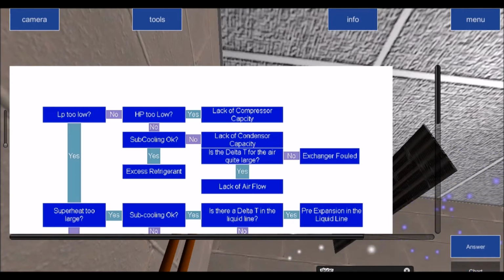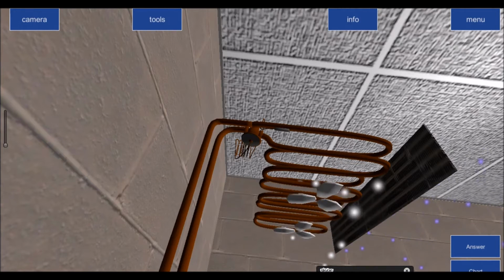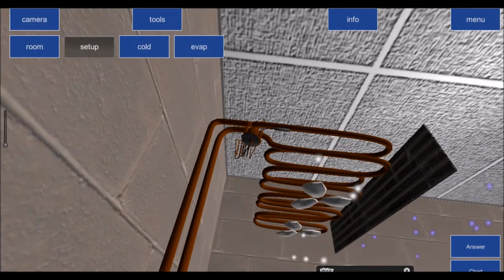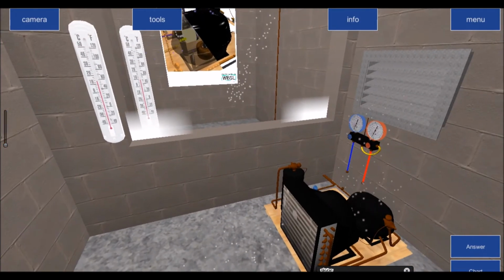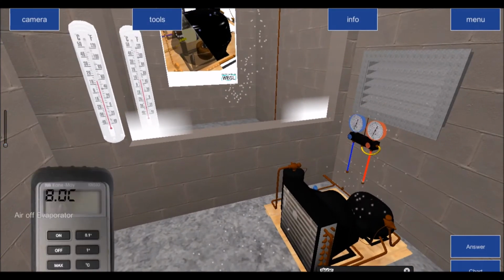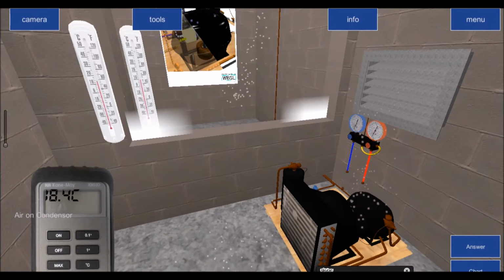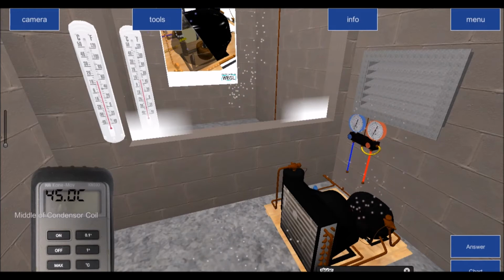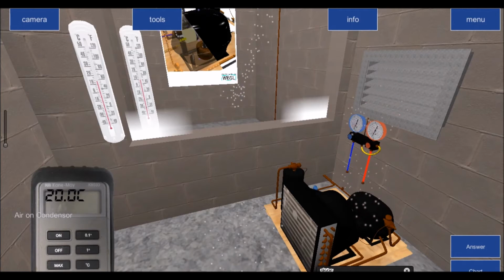So let's go and have a look. Maybe I'm making a mess of this, but anyway, I get confused myself. So head pressure again, air on. Let's get our thermometer. Air on is 20 degrees. Condensing temperature, which is the middle of the condenser, is 45 degrees. So again, we have 15 degrees of a difference there. Is that what we said? Sorry, it's 45, isn't it? 45 is what we have there. Air on to the condenser is 20. So that's 25 degrees of a difference, yeah?